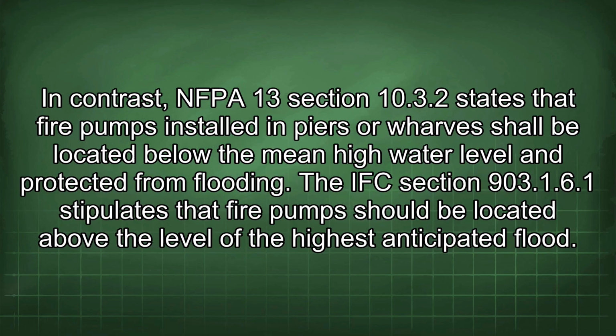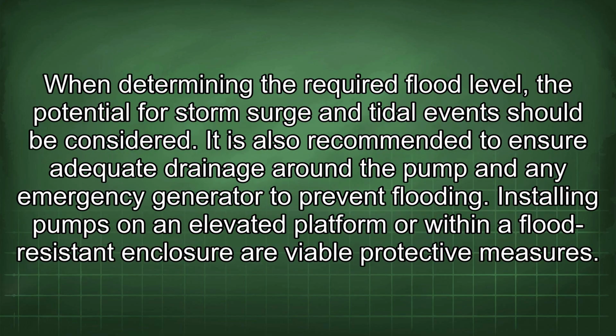The IFC Section 903.1.6.1 stipulates that fire pumps should be located above the level of the highest anticipated flood. When determining the required flood level, the potential for storm surge and tidal events should be considered. It is also recommended to ensure adequate drainage around the pump and any emergency generator to prevent flooding. Installing pumps on an elevated platform or within a flood-resistant enclosure are viable protective measures.